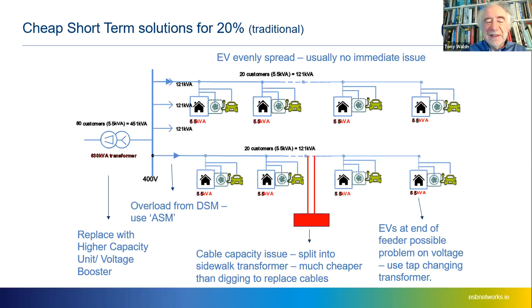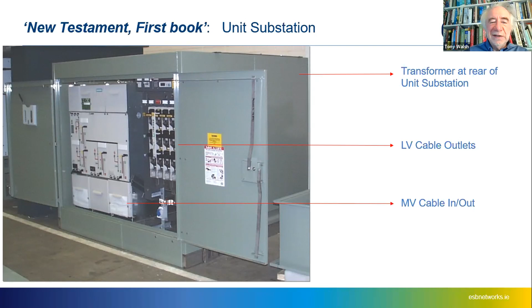The new testament, if you like, is our new technology. Our substations are actually built in the Northeast in what used to be called CG in Cavan, and it's now called Kite PowerTech. So we have here a unit substation which is about 2.5 meters by 2.5 meters. It's 11 cubic meters, doesn't require planning permission. The transformer is at the rear of the unit substation. The LV outlets are on the top, on the right-hand side, where the cables are connected, and the MV cables go in on the left-hand side into the switchgear.